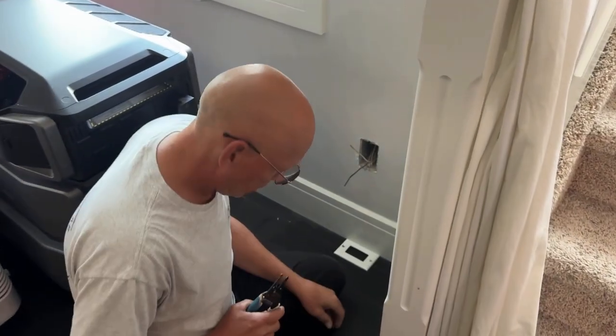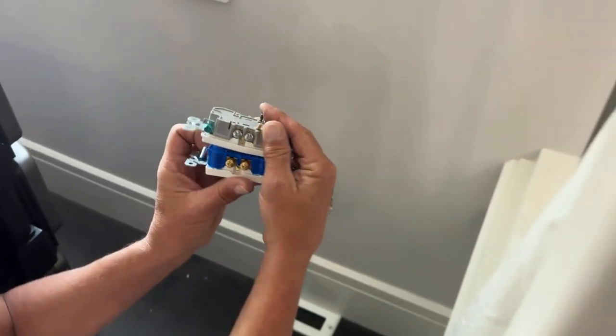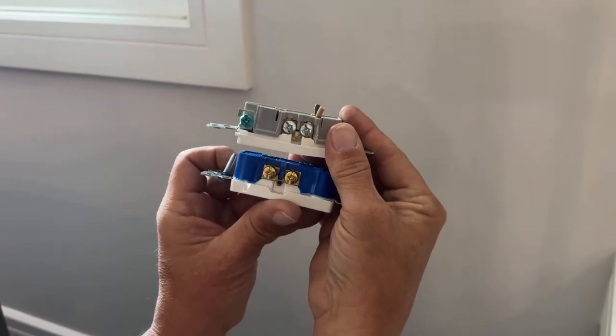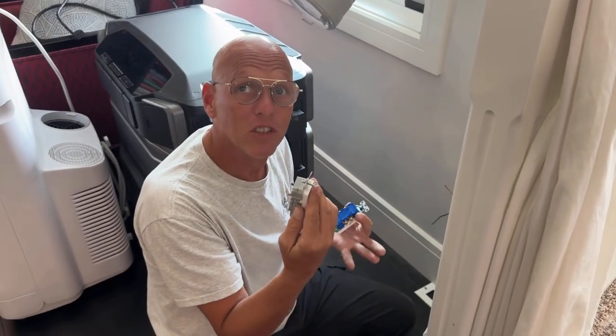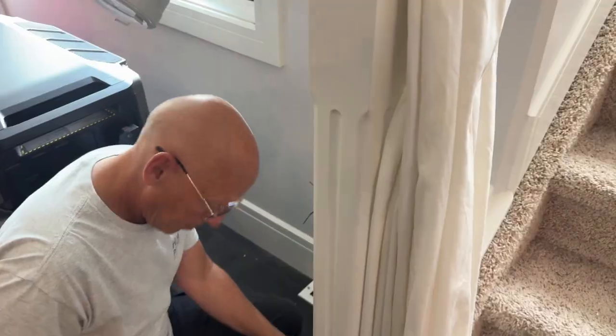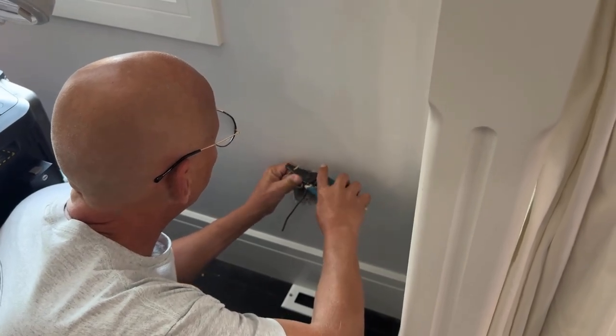Alright, so you've got the original melted plug removed. You can actually see the difference between the two plugs — look at that nice bow on the old one. That's brutal. That thing got hot. First time I've actually seen one that melted on the whole back like that. So what are you going to do differently putting in the new one? I'm not going to backstab it. Attaboy — it's just wrong.